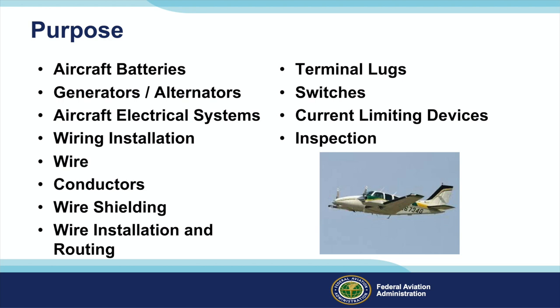Aircraft circuit breakers are what they call trip free. If you've got a hard short, you can push that breaker all day long and the system won't reset as long as that short is there. If you have a hard short and you're able to reset it, you've got a bad circuit breaker, and they do exist.